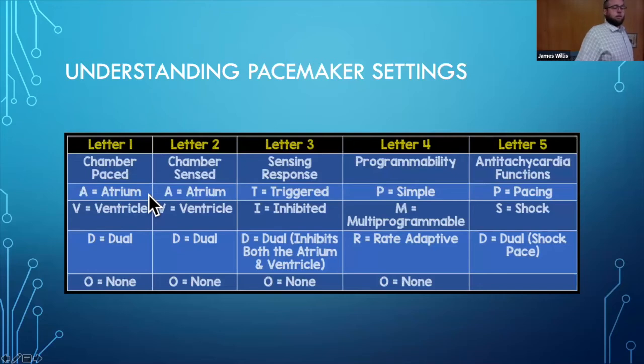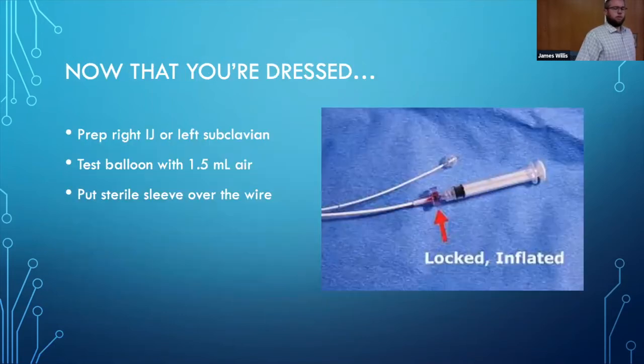So because the pacemaker sensed the electrical activity, the pacemaker is not going to fire because it's VVI, it's inhibited. Versus if we were VVT, in that situation, we would trigger an electrical impulse. But that wouldn't be beneficial in our situation. And then there's letter 4 and 5, programmability and anti-tachycardia functions. I'm not going to go over those right now, but those are other ones to keep in mind.